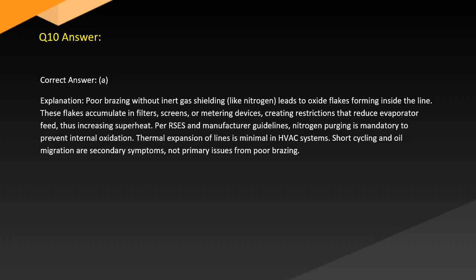Answer. Correct answer: A. Explanation. Poor brazing without inert gas shielding, like nitrogen, leads to oxide flakes forming inside the line. These flakes accumulate in filters, screens, or metering devices, creating restrictions that reduce evaporator feed, thus increasing superheat. Per industry and manufacturer guidelines, nitrogen purging is mandatory to prevent internal oxidation. Thermal expansion of lines is minimal in HVAC systems. Short cycling and oil migration are secondary symptoms, not primary issues from poor brazing.